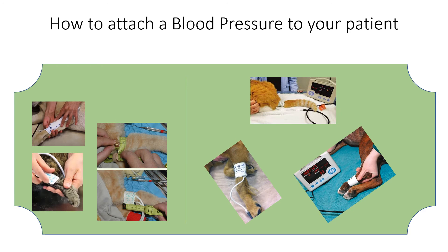The fifth and last accessory we're going to discuss is the non-invasive blood pressure. Non-invasive blood pressures are measured with a cuff fitted to the patient's limb. As you can see from the left side of the screen, there are two ways to measure the correct size. A dog's cuff is 40% of the circumference of the limb and the cat's is 30%. The oscillometric monitor inflates and deflates the cuff as it calculates the blood pressure.